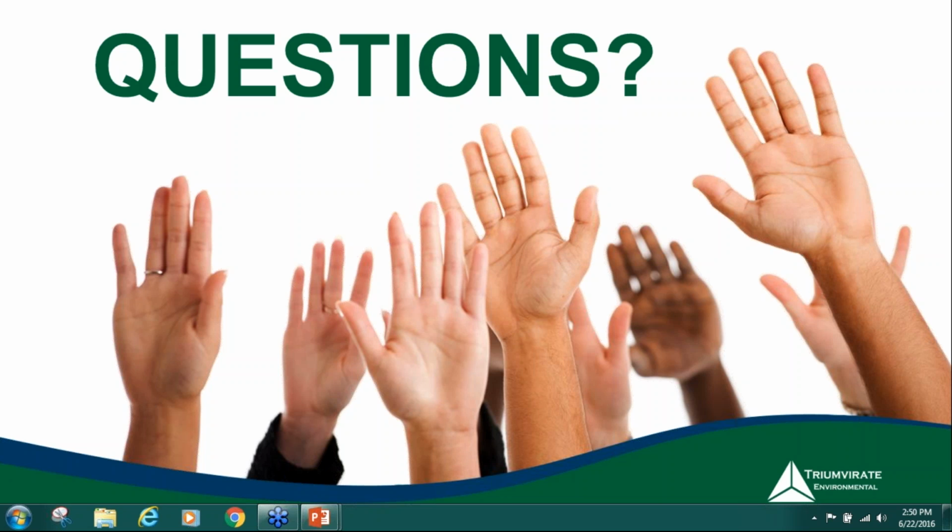Now, if you're not under an SPCC program, but you are covered under state or federal UST program, if you're doing the inspection, you do need to be trained on how to inspect that. You may not be the AB operator who's doing the full inspection, but you're now what's considered the C operator, and you're under the direction, you've been given training in order what to look for and how to do the inspection, and what you should see that isn't correct to call your AB operator.